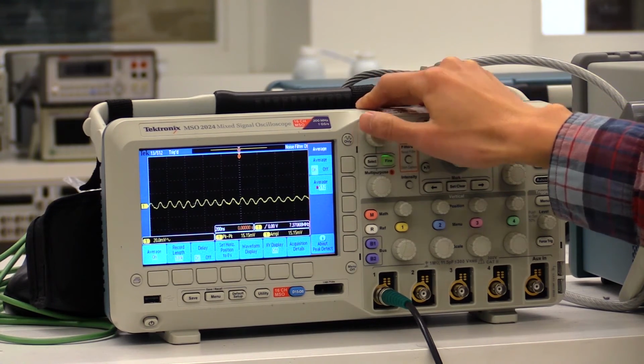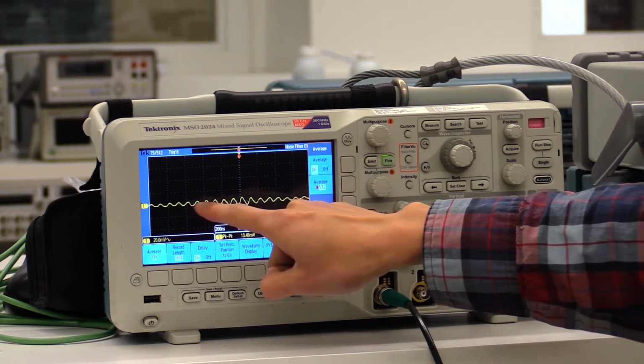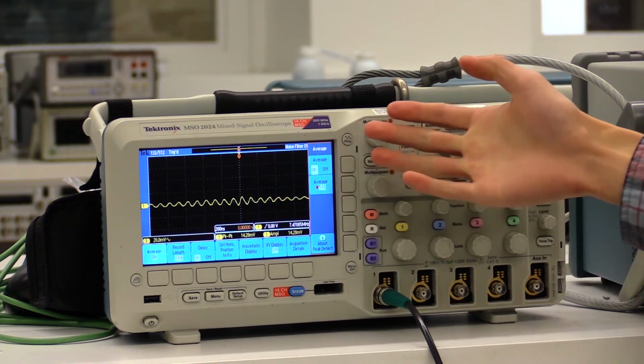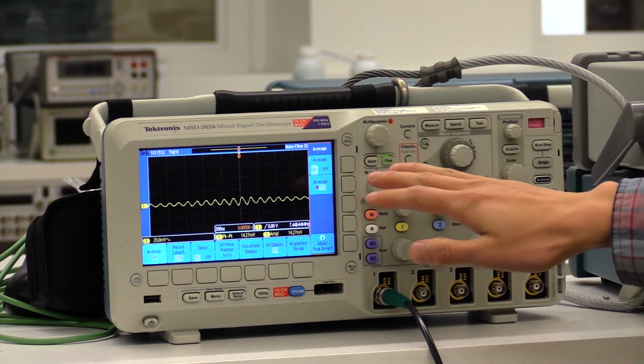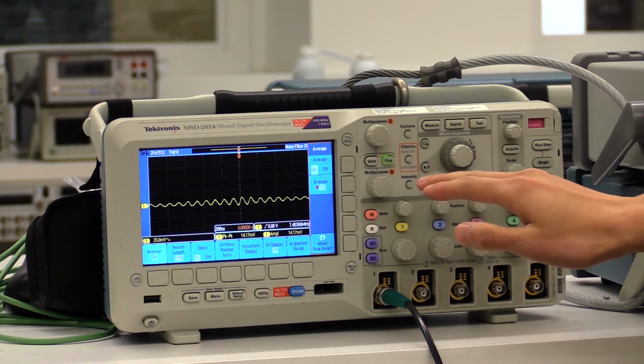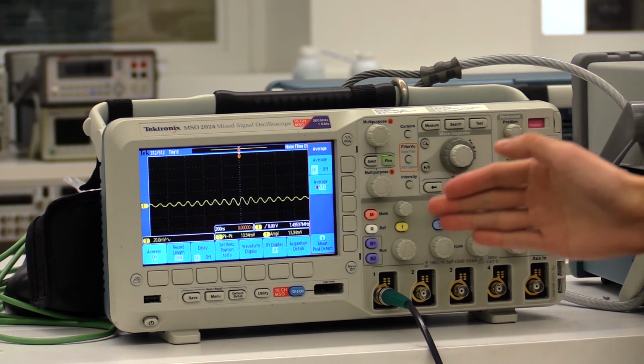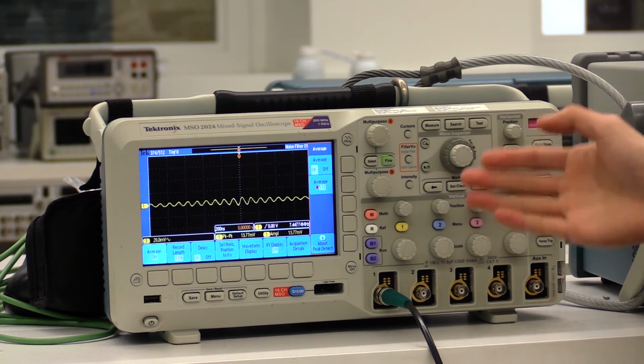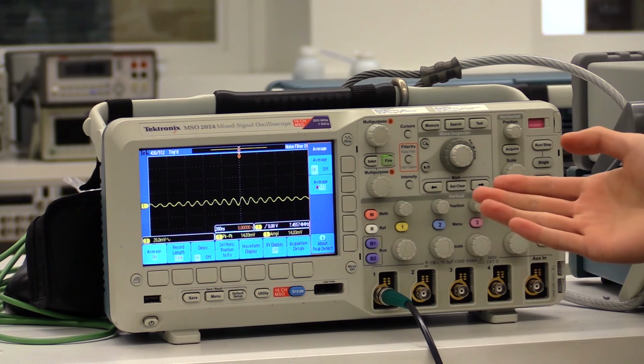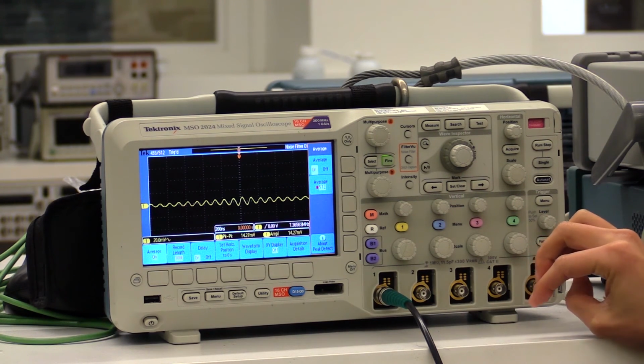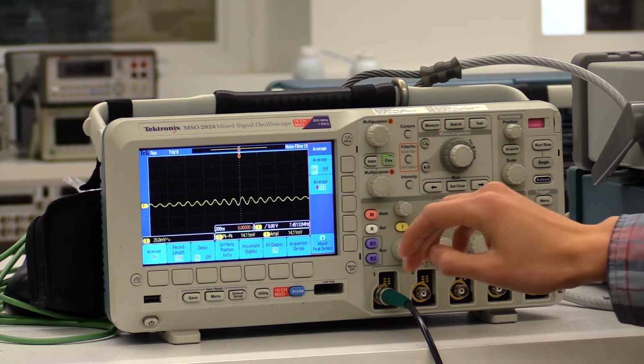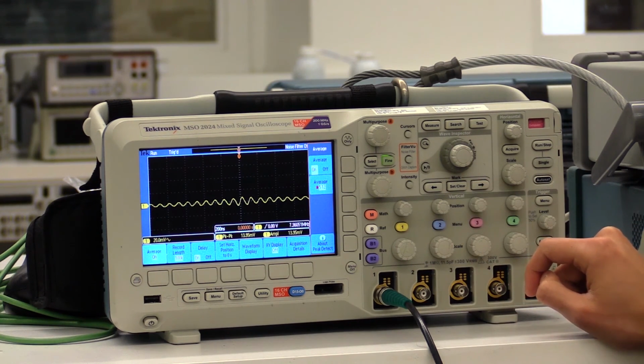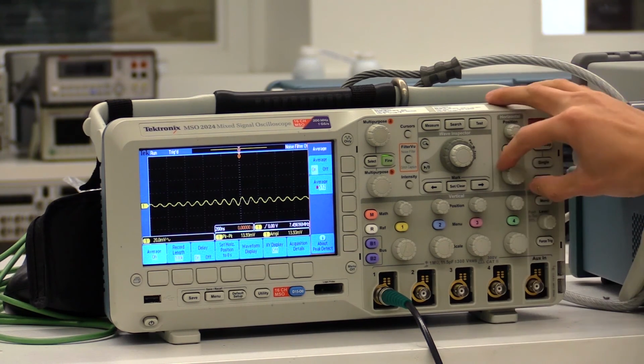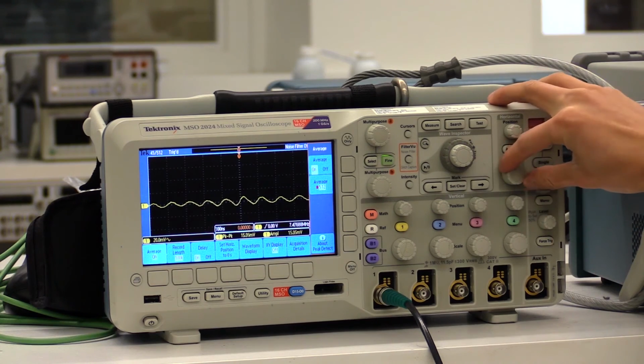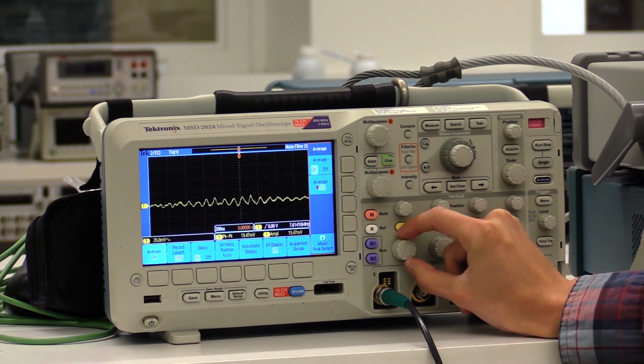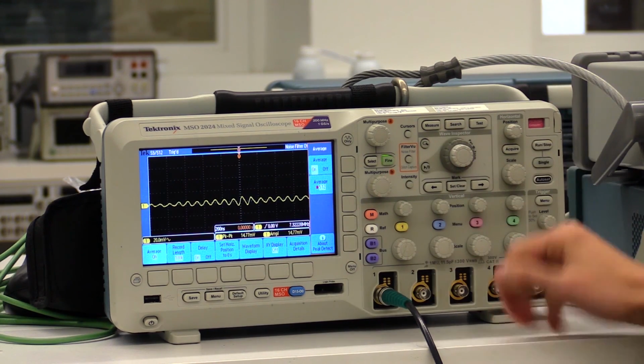If we increase our average really high, we can see that there's this wave that was buried in noise before. You have to be careful when doing this, because if there's a varying signal and it's changing or fluctuating and you don't know if it's going to display a sine wave and you average it, or you forget to turn it off, it's going to display a signal that's not accurate. It's a false signal. So in order to refresh the averaging, say you changed something in your circuit, you can simply adjust your scale and change it back with either one of the horizontal or vertical knobs, and then it'll refresh and take the averages again over time.